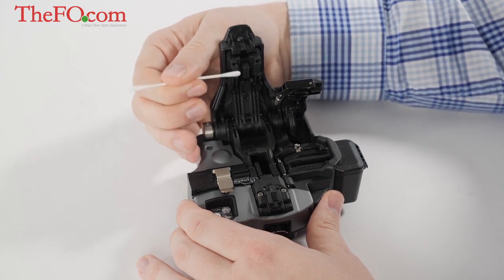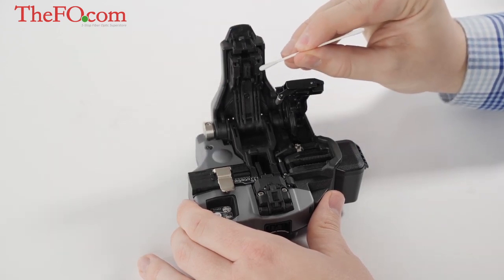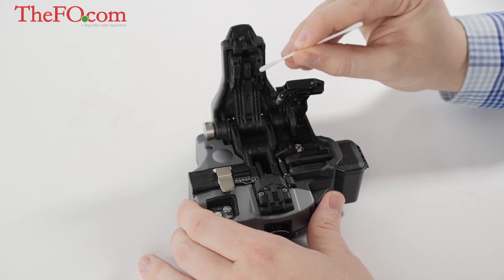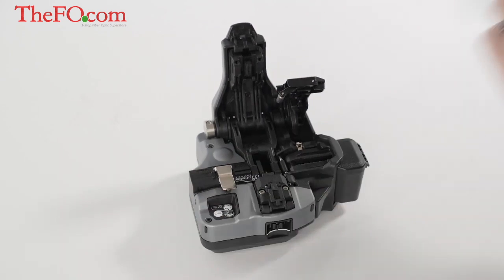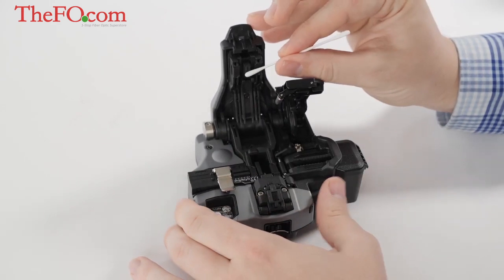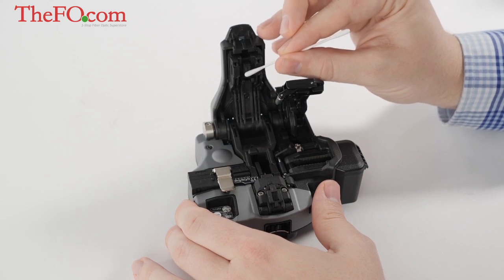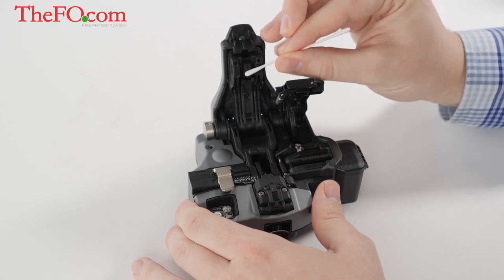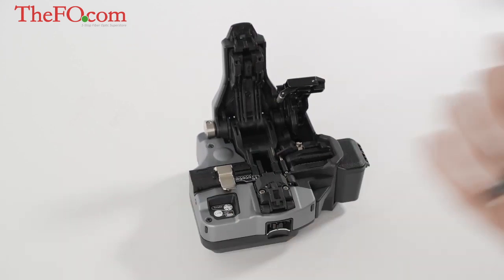You should not clean all 4 pads and anvil with the same moistened cotton swab. Clean no more than 2 pads with a single end of a cotton swab. Rub with a clean, dry, lint-free cotton swab to remove excess alcohol and any remaining loose debris.